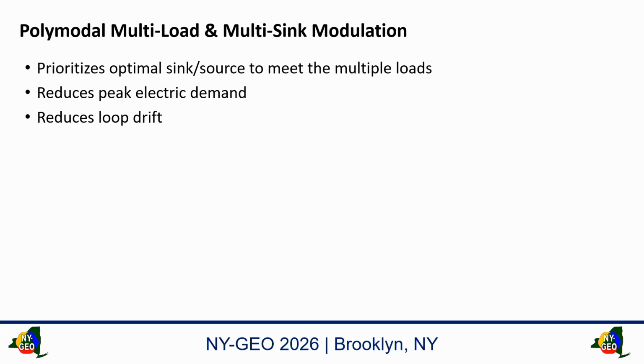Let's take a heat pump that has a COP of 4. When it's heating, it takes 3 from the earth, adds 1 from the utility, and puts 4 into the space. That same air handling unit, when I go to cooling, turns around, takes 4 from the space, adds 1 from the utility, and puts 5 in the ground. So now my ground loop is already 5 over 3. I'm unbalanced. But the load was balanced. It's 4 and 4.